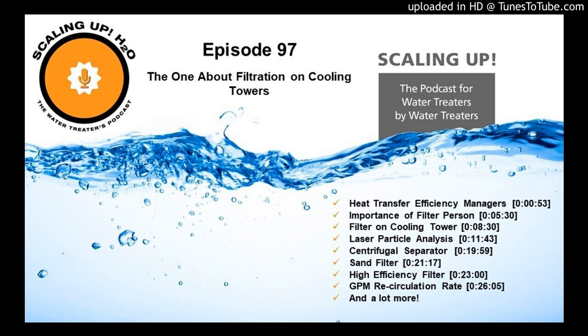Usually the other terms are particle volume, particle count, surface area, total suspended solids. These are pretty confusing subjects that you get when you get a particle analysis result. That can be pretty confusing, to the customer and to the water treater. Particle volume is the total volume of all the particles that are in the water. If you squish it all together and make all those particles into one ball, that's the particle volume, measured in cubic microns. The volume is the size of it.